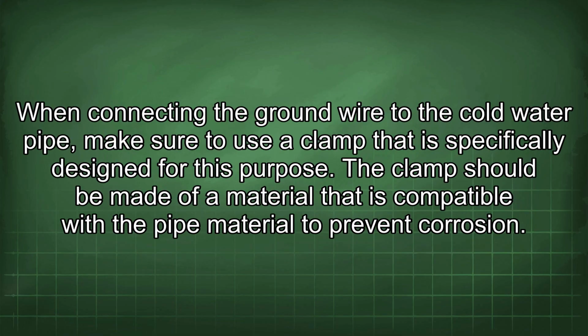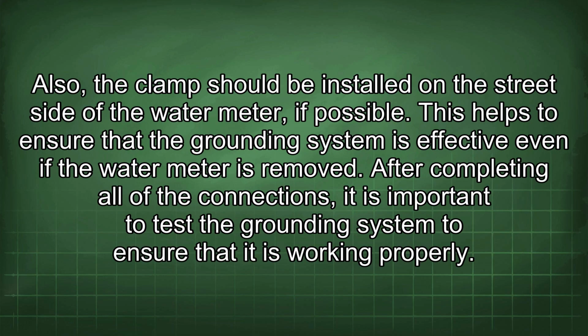When connecting the ground wire to the cold water pipe, make sure to use a clamp that is specifically designed for this purpose. The clamp should be made of a material that is compatible with the pipe material to prevent corrosion. Also, the clamp should be installed on the street side of the water meter if possible. This helps to ensure that the grounding system is effective even if the water meter is removed.